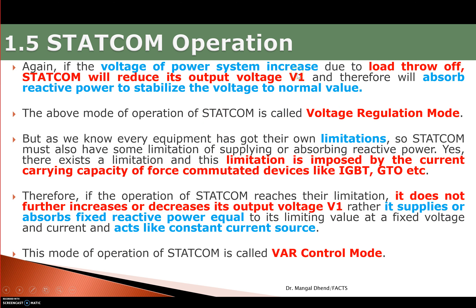When the power system voltage increases — for example, during low load periods such as nighttime or afternoon — STATCOM reduces its output voltage V1. This causes power to flow from the power system into STATCOM, so STATCOM absorbs reactive power. By absorbing reactive power, STATCOM stabilizes the system voltage back to its normal value. This is the Ferranti effect scenario, where absorbing reactive power prevents the voltage from rising too high.